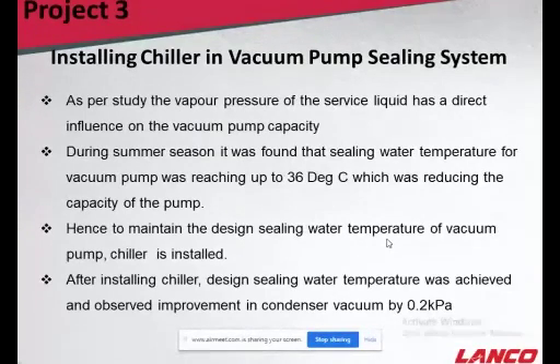This is the installation of a chiller in the vacuum pump sealing system. It's a very interesting point. Actually, we tried to improve the pump performance, and the vacuum pump is a very critical part of the system in the vacuum, and we realized its importance during the peak summer. So in this project, we took this pump and recorded all the parameters of the running pump. But in the running pump, we found that the sealing water temperature was very far from the design values as per the OEM.